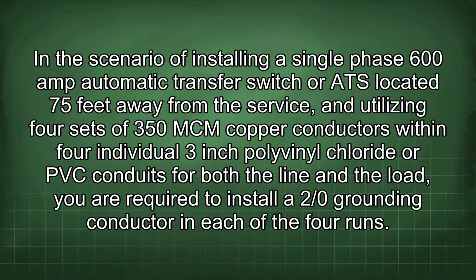In the scenario of installing a single-phase 600-amp automatic transfer switch, or ATS, located 75 feet away from the service, and utilizing 4 sets of 350 mcm copper conductors within 4 individual 3-inch polyvinyl chloride or PVC conduits for both the line and the load, you are required to install a 2/0 grounding conductor in each of the 4 runs.